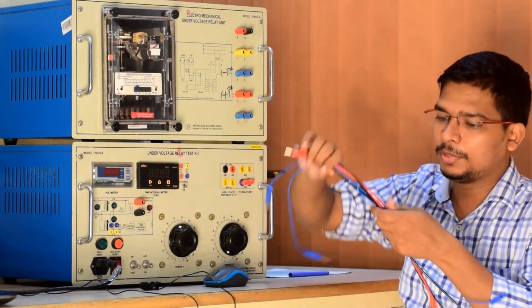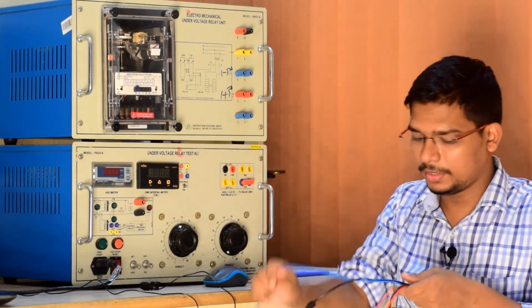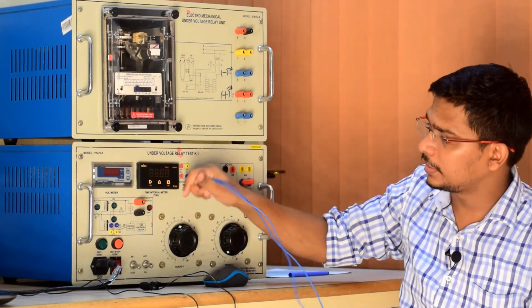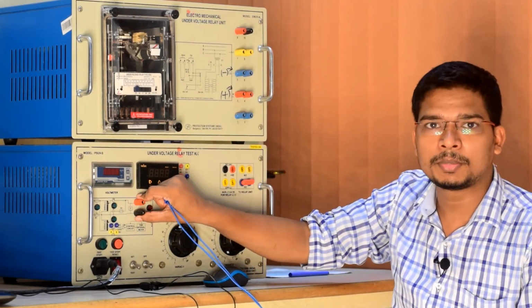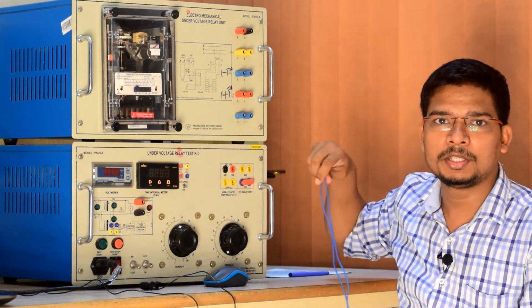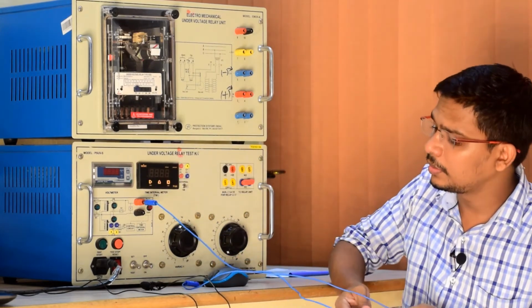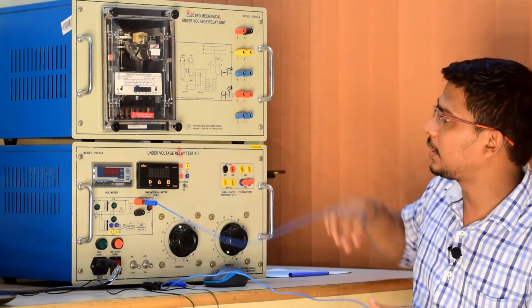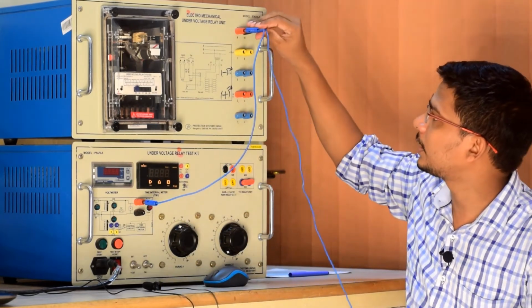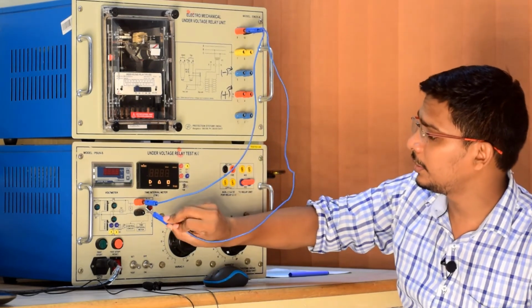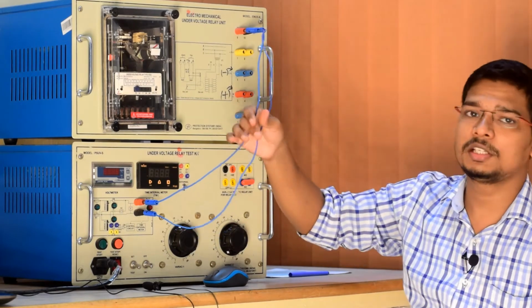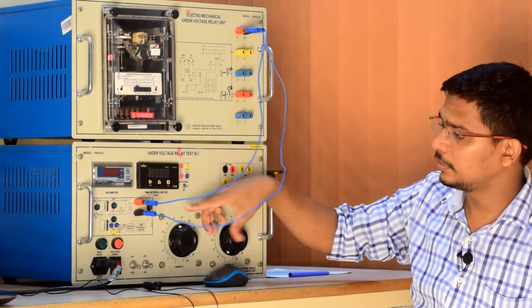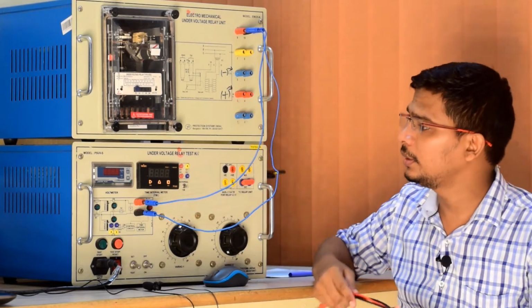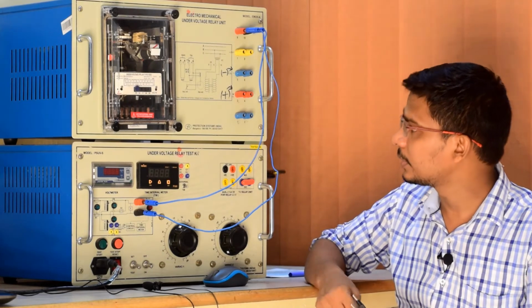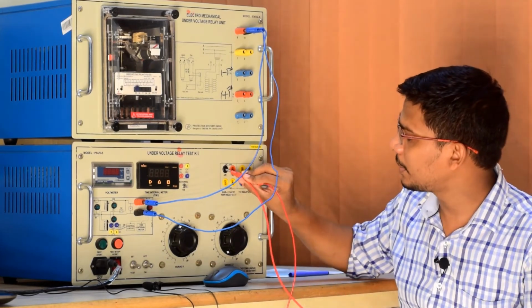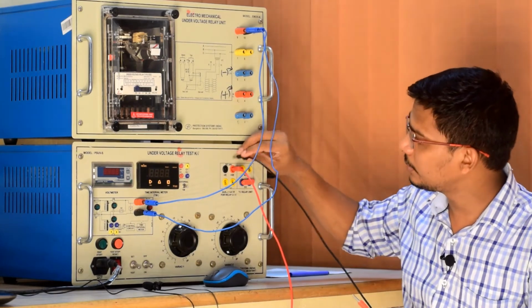So these are the banana pins, and as I have told you, these two terminals are the output of the power supply unit and these two terminals are the input of the relay unit. So the output of the power supply unit will be connected to one input terminal, and then terminal number 10 of the relay will come to the power supply input. So this is the voltage we are applying to 9 and 10 from the power supply terminals of the under voltage relay test unit. Next we have to give the auxiliary power supply, plus and minus.